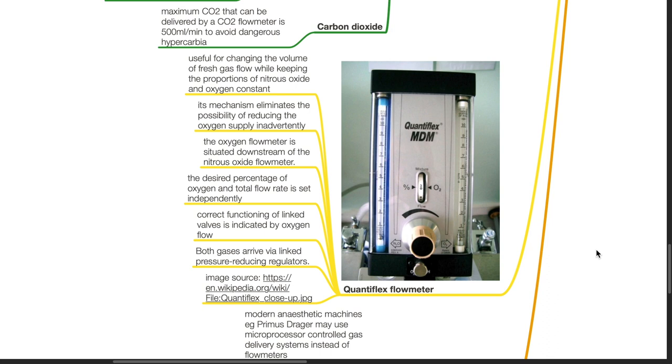The oxygen flow meter is situated downstream of the nitrous oxide flow meter. The desired percentage of oxygen and total flow rate is set independently. Correct functioning of linked valves is indicated by oxygen flow. Both gases arrive via linked pressure reducing regulators.